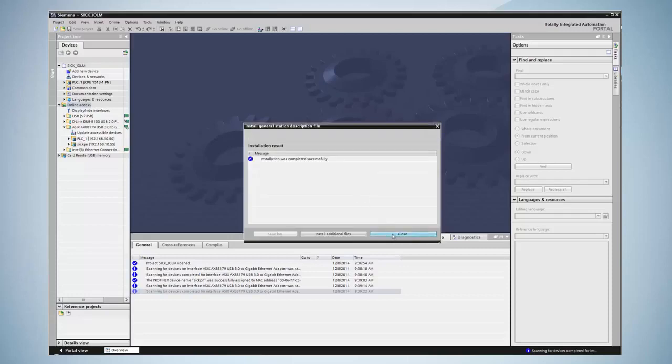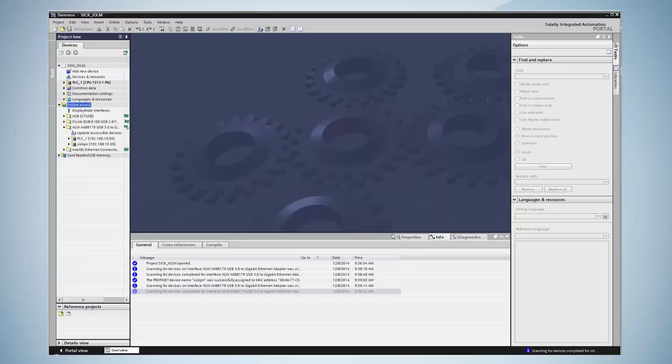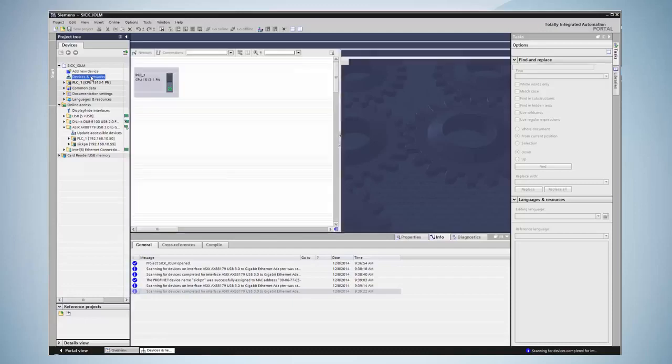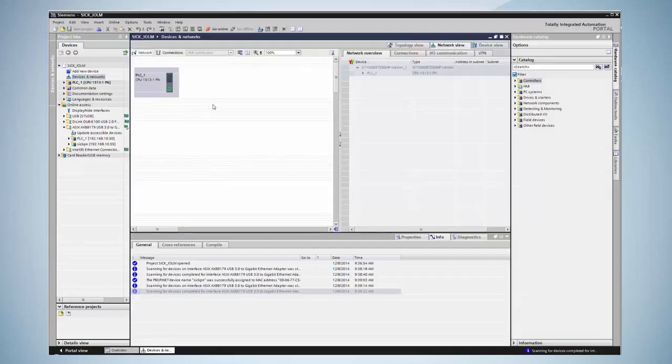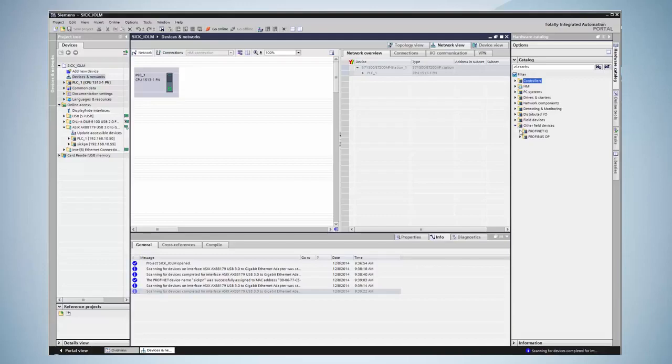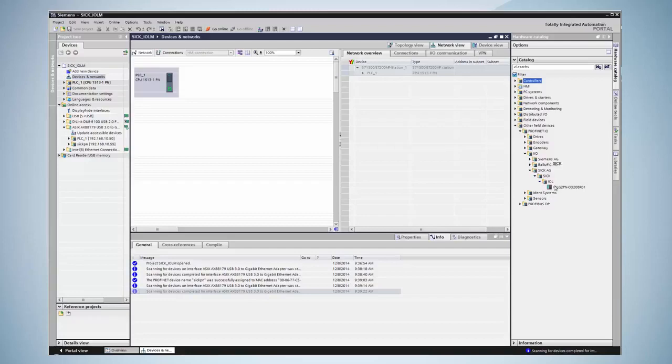The existing PROFINET network is displayed by clicking on device configuration network view. The IO-Link master is displayed in the hardware catalog under other field devices, PROFINET IO, IO, SICK AG, SICK IOL. The master can now be added by drag and drop into the left window.